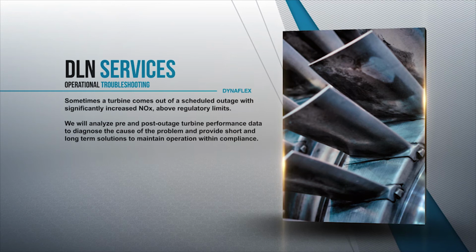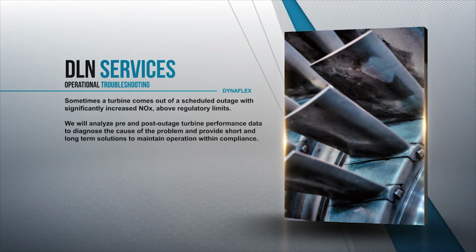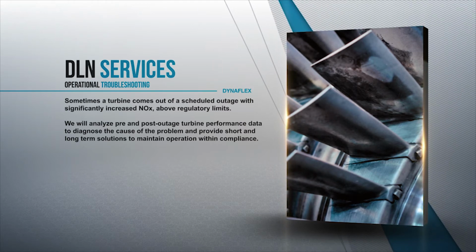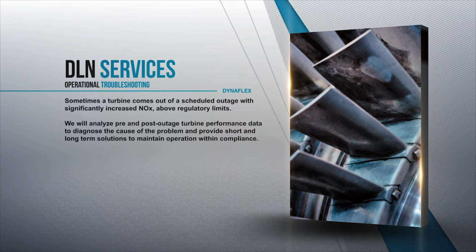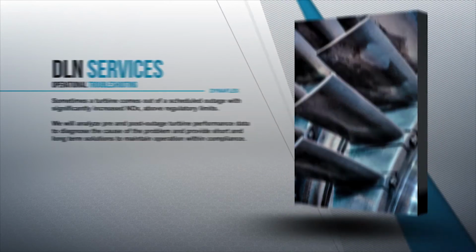Sometimes a turbine comes out of a scheduled outage with significantly increased NOx above regulatory limits. TTS will analyze pre- and post-outage turbine performance data to diagnose the cause of the problem and provide short- and long-term solutions to maintain operation within compliance.